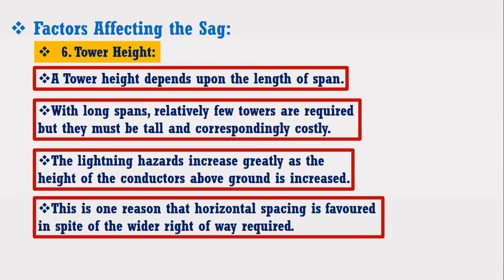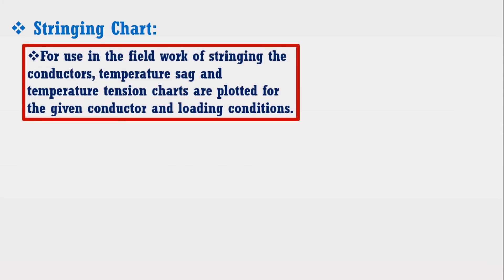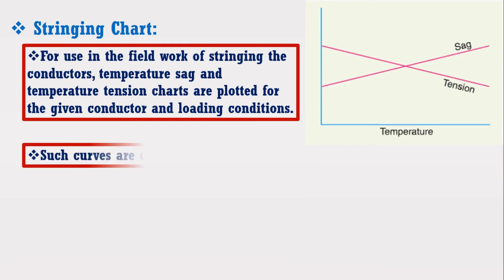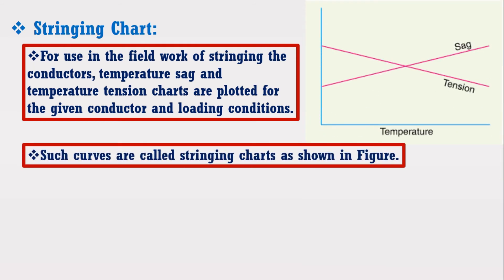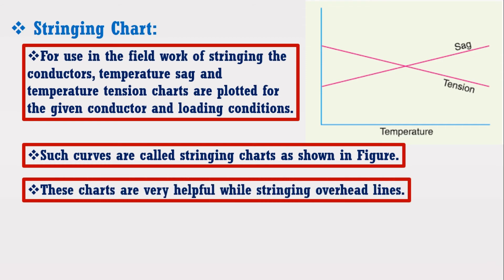I am going to discuss another important term used with respect to sag and tension, known as stringing charts. For use in the field work of stringing the conductors, temperature-sag and temperature-tension charts are plotted for the given conductors and loading conditions. Such curves are called stringing charts, as shown in the figure. These charts are very helpful while stringing overhead lines.